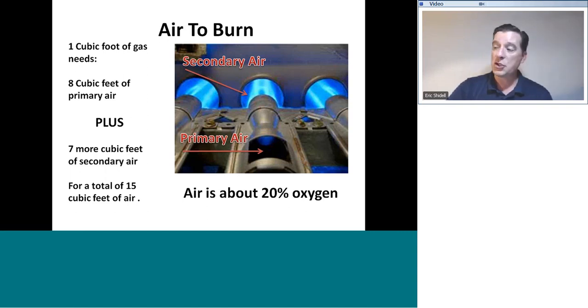And all of our burners are shaped and sized and designed to create that specific mixture when the fuel is delivered at that specific pressure. And we'll talk about what that pressure is a little bit later. That air is drawn in to mix with the fuel, and it is able to sustain a flame down at the end of the burner. There's additional air that joins the party, however, and that's called secondary air.